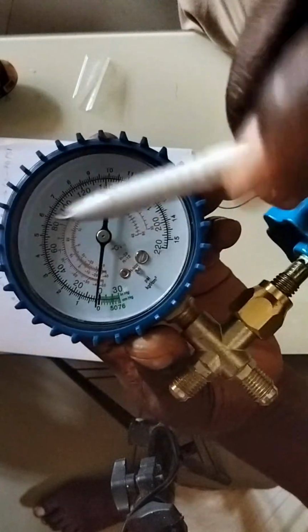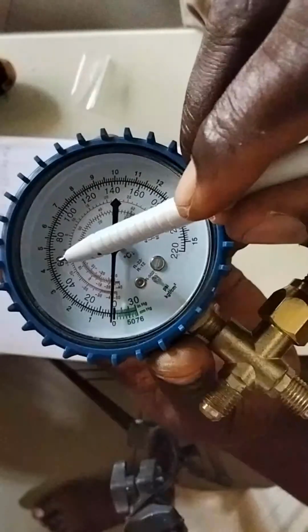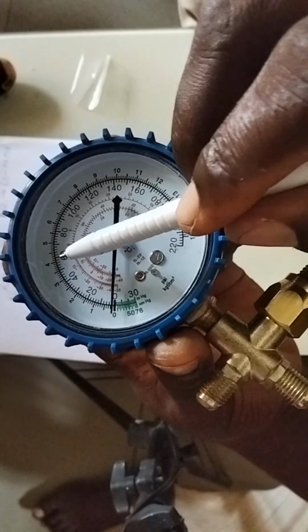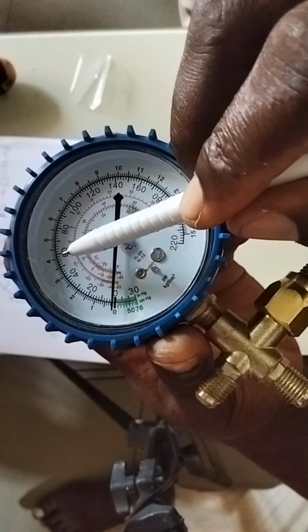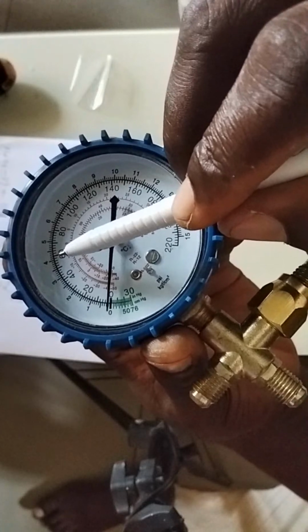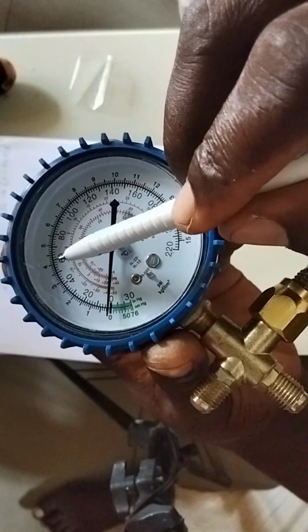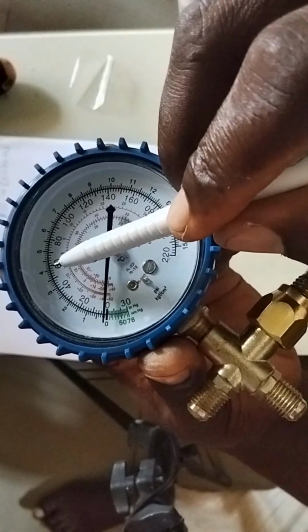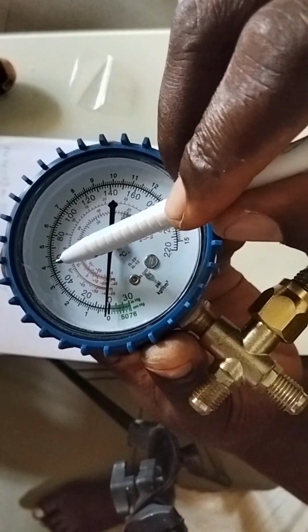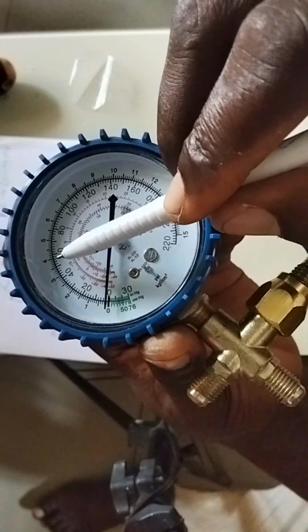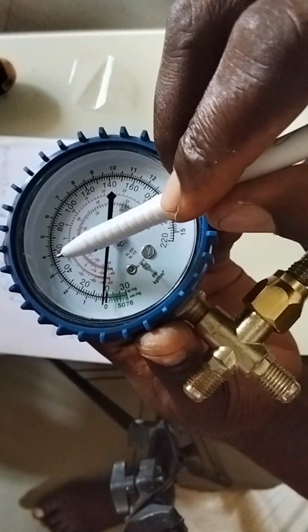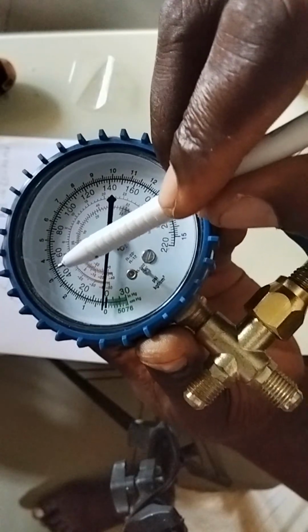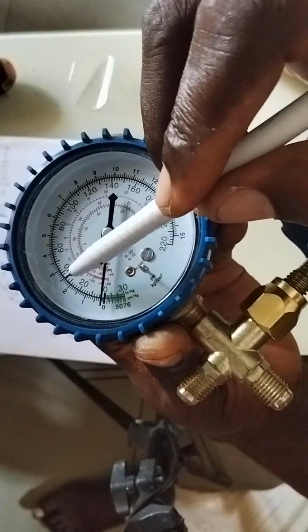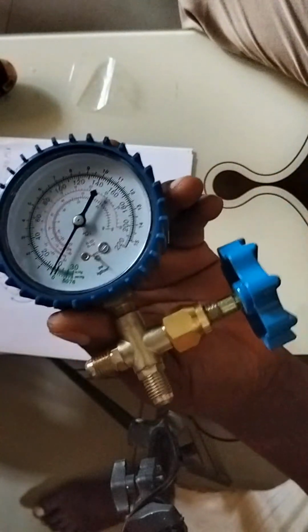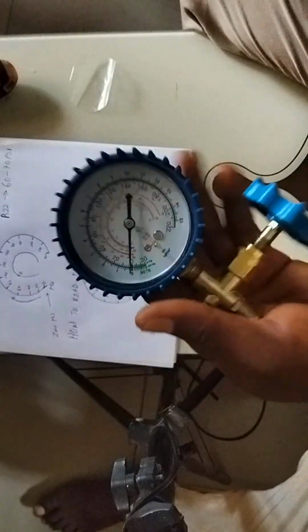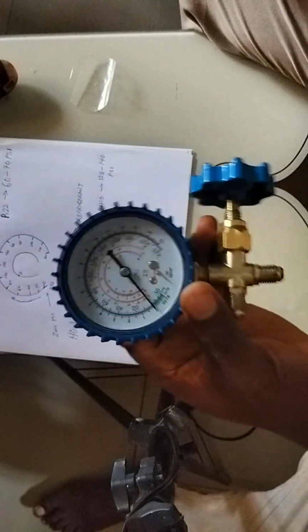Like for what you have here now, if you have a gauge reading at 60 psi, and you feel there is a leakage on the system, you leave it there for like 20 to 30 minutes. Before you come back to observe your system, you will see that there will be a psi drop to the left. It will be either 1 unit or 2 units or 3 units. If it's a leakage that is very, very obvious, you see that it will drop a whole lot down to this point or even come down a little bit more, for you to notice, okay, there is actually a leakage on this system. That is how we notice it, and that is how we know that there is a leakage on the system using a gauge.